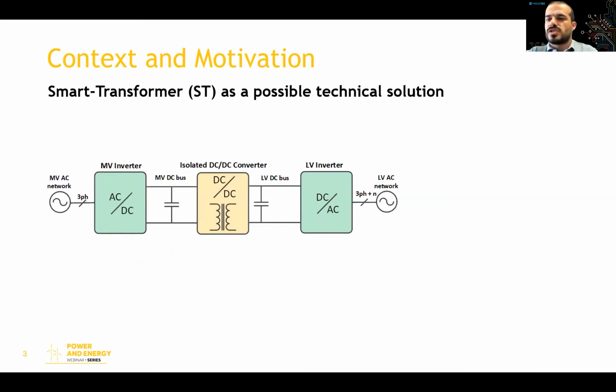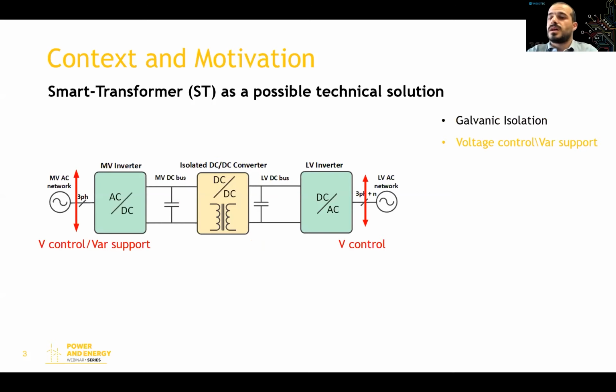In order to show the potentials of this solution, I enumerated some functionalities that can be attributed to this equipment. One of them, which is already present in the traditional equipment, is the galvanic isolation, always needed for safety reasons. And on top of that, we can also have voltage control and reactive support. And contrary to the traditional low-frequency transformer, the smart transformer can control the voltage at its terminals independently.